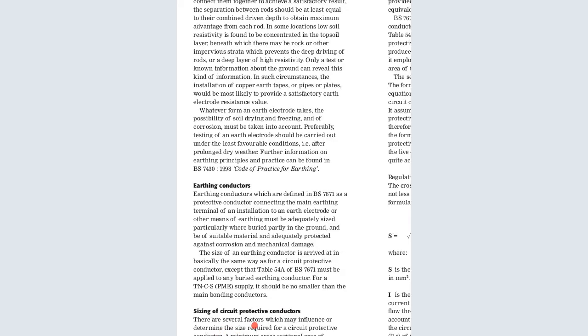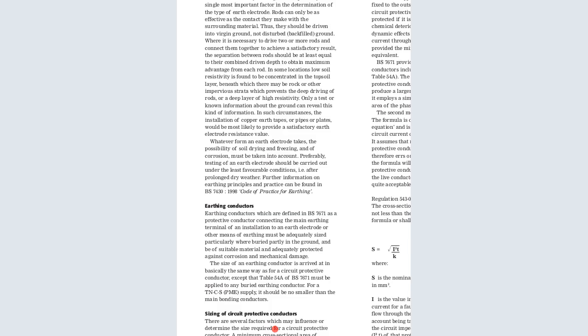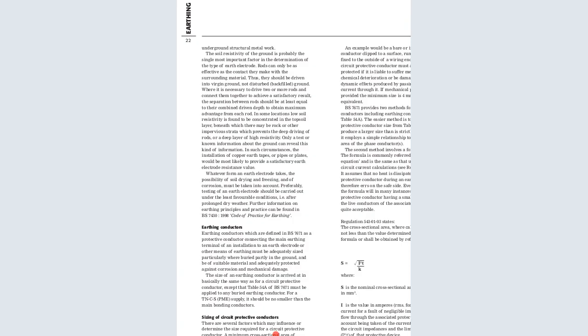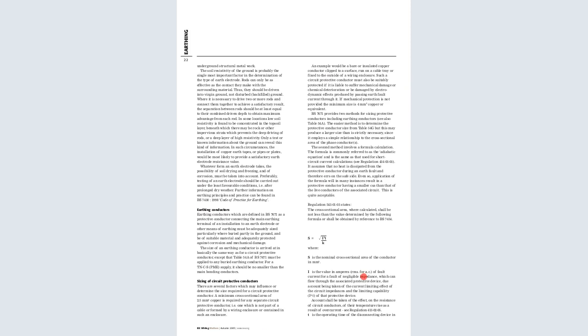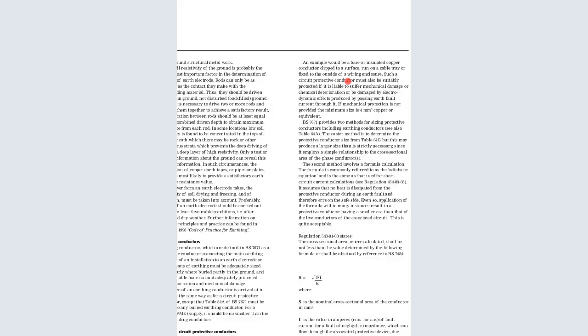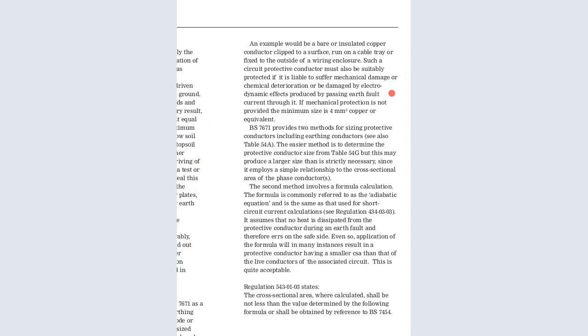There are several factors which may influence and determine the size required for the circuit protective conductor. A minimum cross-sectional area is needed. A minimum cross-sectional area of 2.5 millimeter square copper is required for any separate circuit protective conductor. An example would be a bare or insulated copper conductor clipped to the surface, run on a cable tray, or fixed to the outside of the wiring enclosure. Let me zoom out so that it can be very clear.